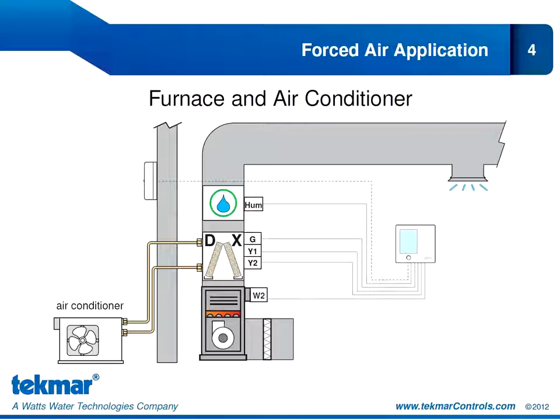The first traditional application is a forced air system for heating and cooling through standard ductwork. The 557 is controlling 1 stage of furnace through the W2 relay connections, and an air conditioner is providing 2 stages of cooling through the DX coil with the Y1 and the Y2 relay connections. We're also controlling a fan with our G connection and humidification through an accessory relay. So this is a standalone 1-stage heat, 2-stage cool application.